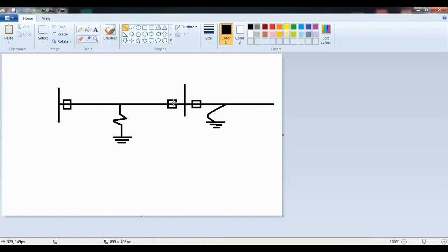However, in long lines, the line impedance is much greater than the arc resistance values. So even if the fault occurs in the critical area between them, if you add 10% or 20% more, they won't go outside. For example, even if the fault was 60% or 70% away from this breaker, it will be seen at about 90%, for instance. But the next breaker still sees it where? Inside zone 1. Therefore, in underreach, the understanding between the two relays is achieved through zone 1.